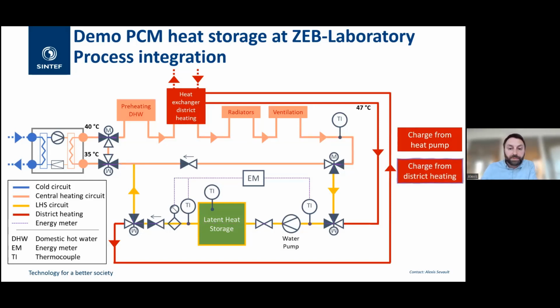Another way to charge is from the district heating - that's the red box. The design temperature, ideally before we built the whole building, they told me would be 47 degrees, but it hasn't been so high - we get 40, 41 degrees in general. But again, that's enough to melt the PCM, so that's working quite well. I was hoping it would be like a fast charger, but it's never been as high as 47. Anyway, it's high enough - that's enough to charge independently of the local heating system.